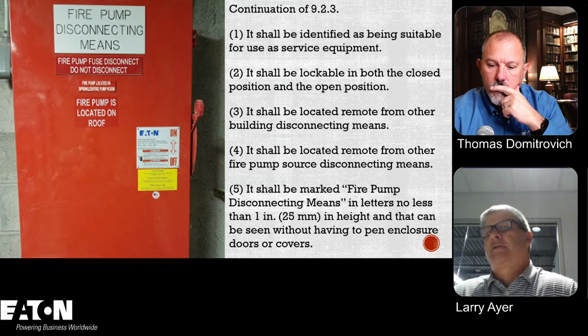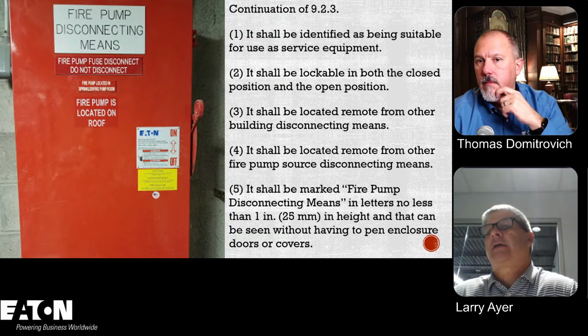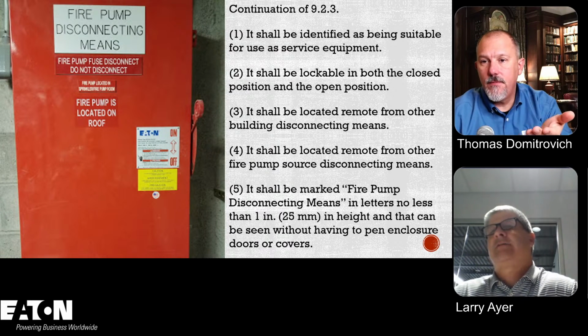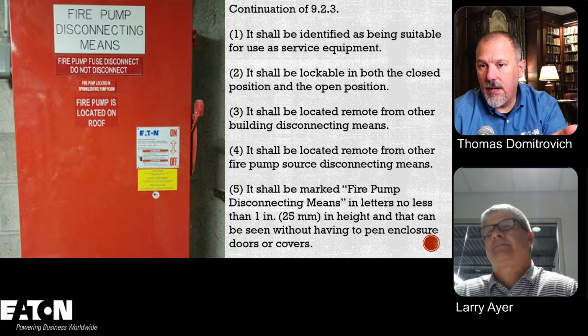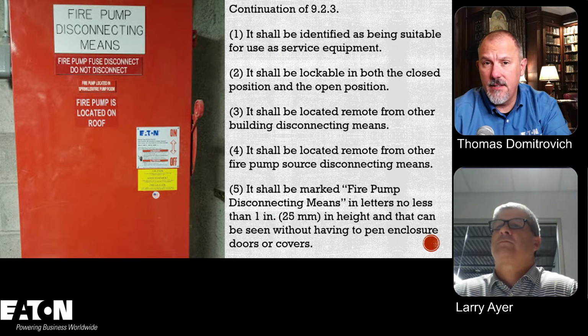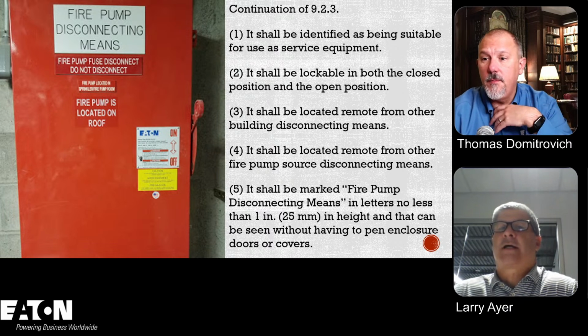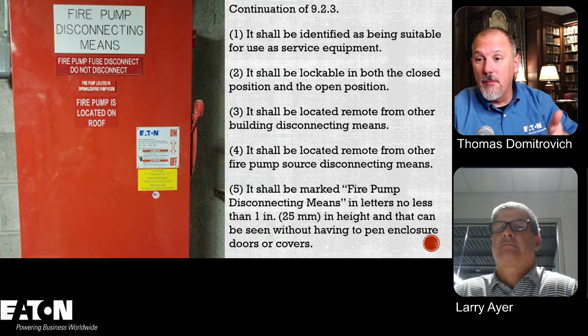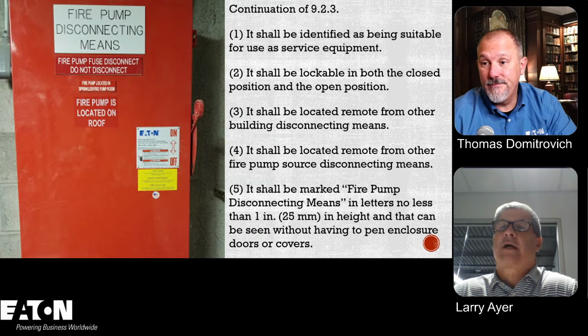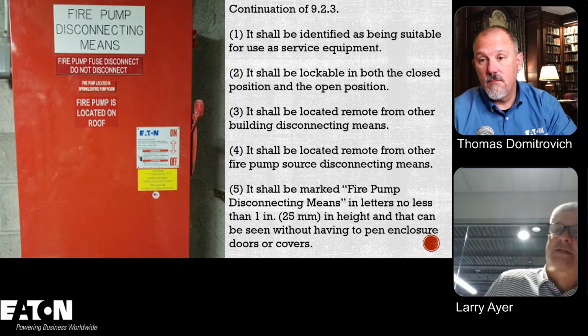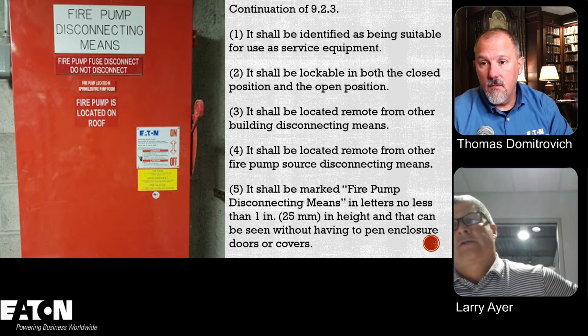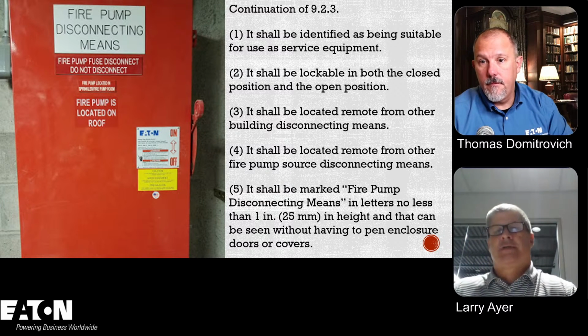And maybe you have to trench to get the conductors outside the building, to put it remote from the other building disconnecting means. So 3 is kind of tricky in trying to work around existing building conditions. Yeah, and I guess 5. Go ahead. But just the whole aspect of remote, I mean, that's a pretty vague statement just in general. Remote to me might be 10 miles away, but remote to you might be 10 feet away. Correct. And the last thing is it shall be marked fire pump disconnecting means in letters no less than 1 inch in height. So those are kind of just the requirements for the disconnecting means.